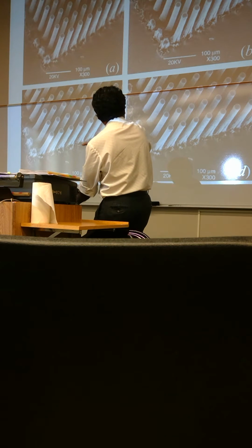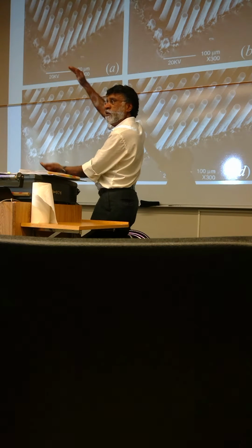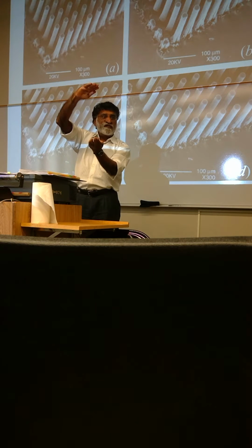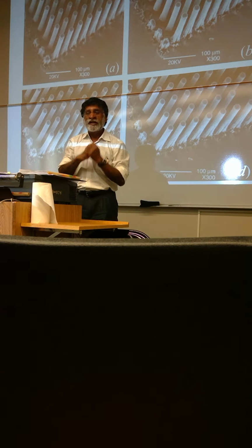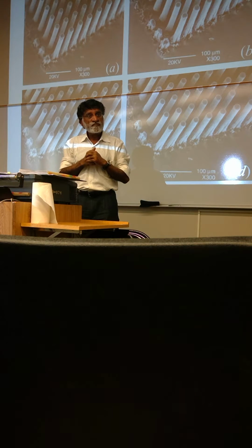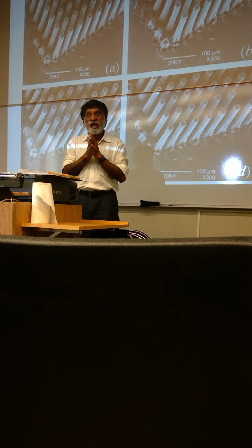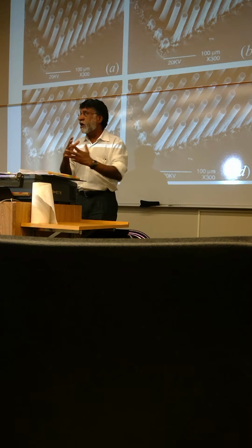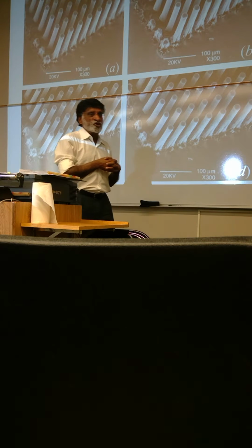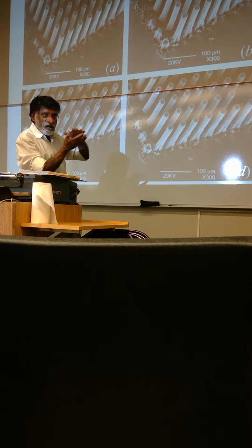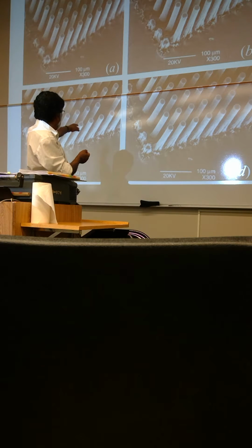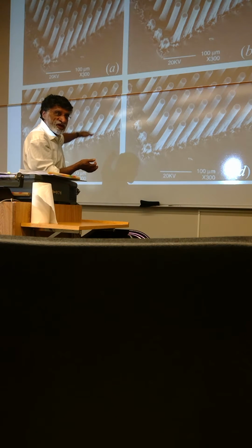And you can see that these are all pillars, and there is a different range over which they stay in focus. Some of them stay in focus all the way through, some of them not. This is what you play with: the aperture size and the working distance. Because it's an electronic lens, you can change its focal length by changing the current. So is the best one the C? It depends on what you want to see. If you want a large range with somewhat poorer performance, then you would go A. If you want optimal performance for the range that you're working with, you go with C.